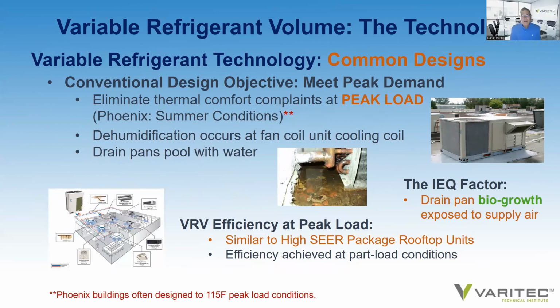Well, in Arizona, we see many times VRV systems used with untempered outside air, and it's understandable. It's to reduce the first cost of a design. However, these conventional designs are designed where the variable refrigerant system is designed to meet the peak load demand. And in order to eliminate thermal comfort complaints, we have to design to that peak load. Dehumidification, of course, for the outside air and the building moisture gain due to occupants, bathrooms, sinks, etc., occur at the indoor air handler cooling coil.